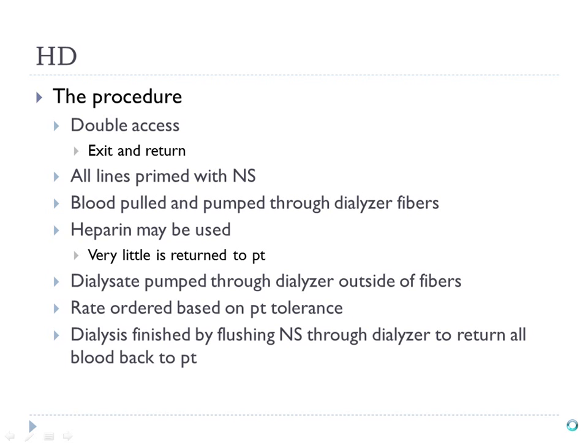During dialysis, blood is pulled from the patient, run through the tubing and pumps, through the dialyzer, and back to the patient. When the prescribed time and fluid removal are complete, you don't just stop and disconnect — you flush saline through all the tubing to return all the blood to the patient.